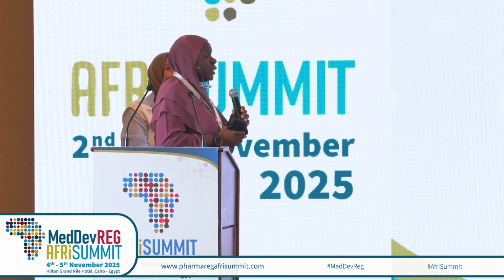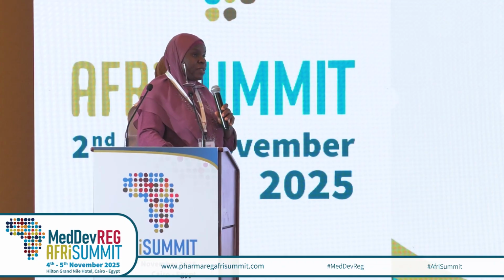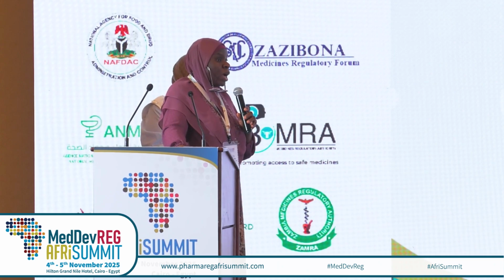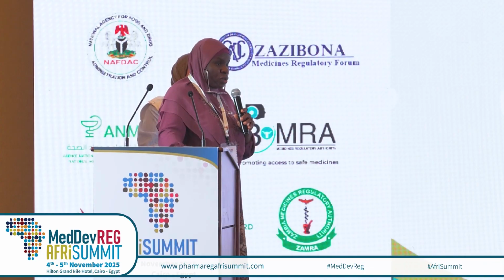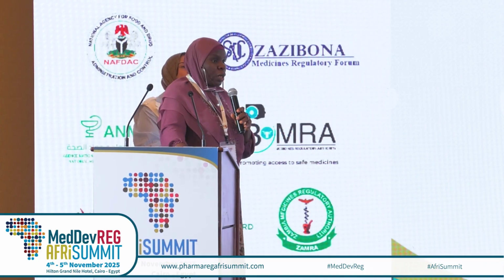Your second question was on, what was that? Oh yeah, risk. So the risk classification is a multi-level verification. The first one will be done during the dossier screening, because dossier screening is basically for completeness, ensuring that the different sections of the TOC have been covered, the required information is there and all of that. So there isn't really an in-depth review at that stage. The final verification of the risk classification, as stated by the manufacturer, will be done after the submission, when the full dossier review is ongoing. So that's how we run that process.